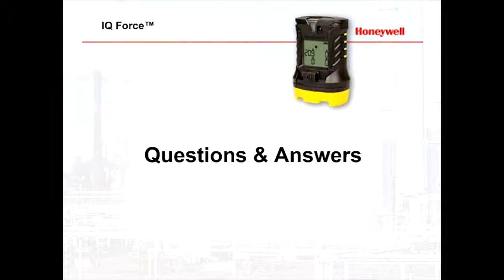Nobody can predict that, like really heavy poisoning on an LEL sensor. You just don't know when that's going to happen. But we can predict a lot of the stuff that happens slowly over time. Even with an LEL sensor, if it's being slowly poisoned over time, which happens in a lot of cases, maybe once a month guys get exposed to a little bit of silicones as part of their job, and that shows up over time. You'd be able to pick up things like that in the sensor trending as well.